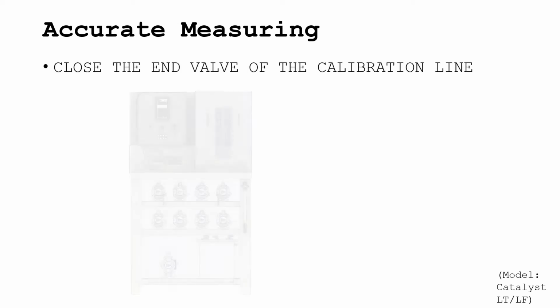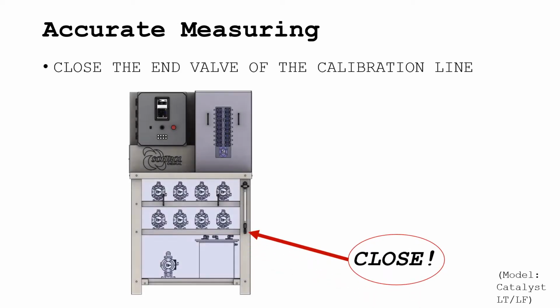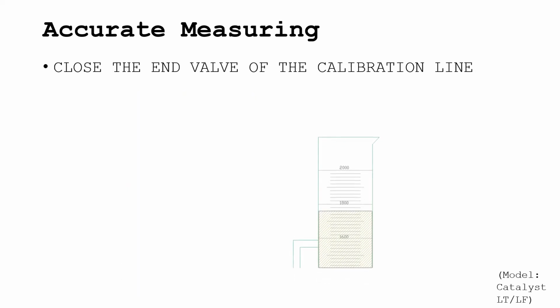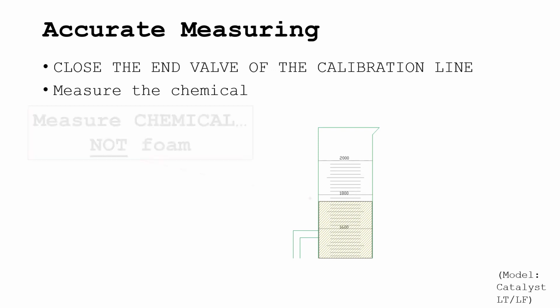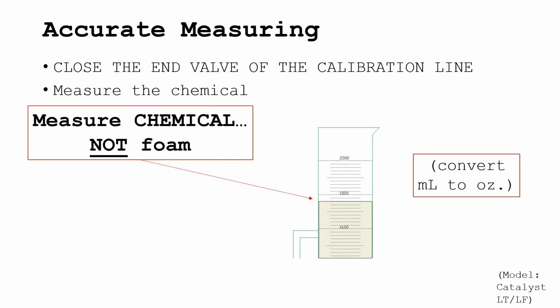To accurately measure the chemical, first close the valve at the end of the calibration line so it does not leak, then place the graduated cylinder on a level surface and read the amount of chemical, making sure not to measure the foam and to convert units if necessary.